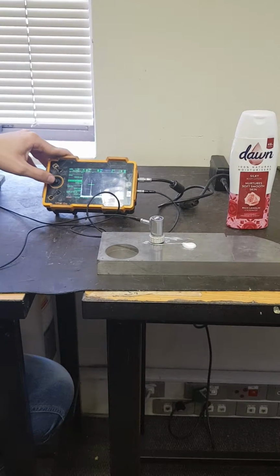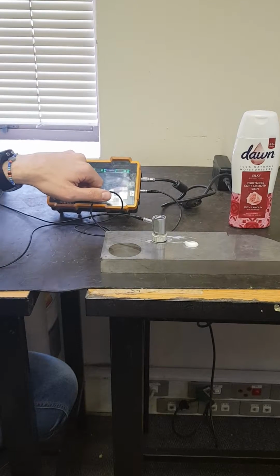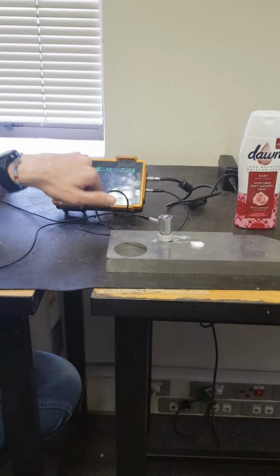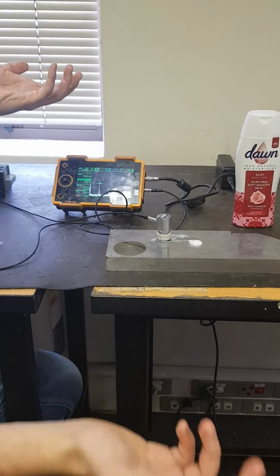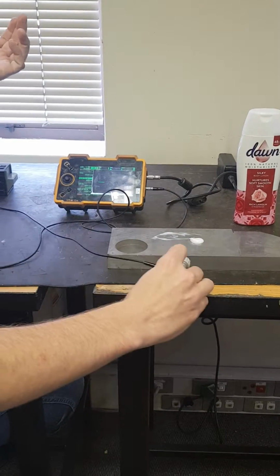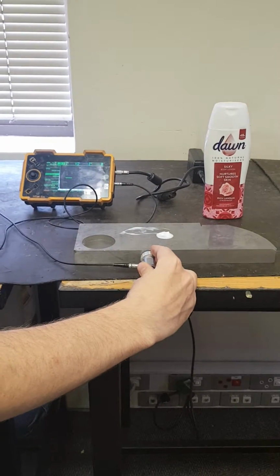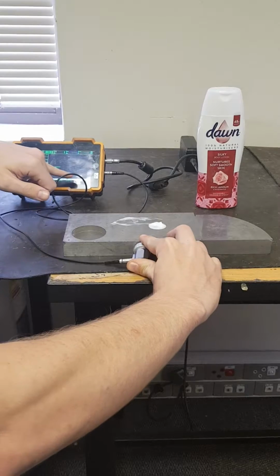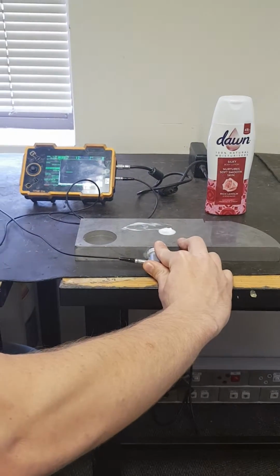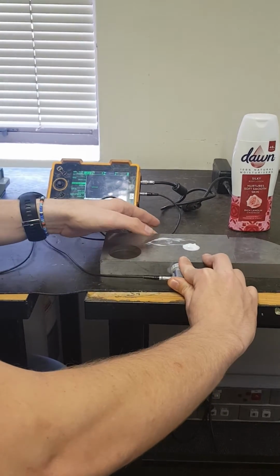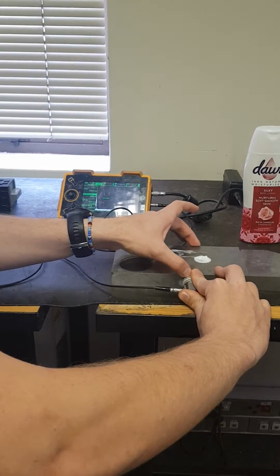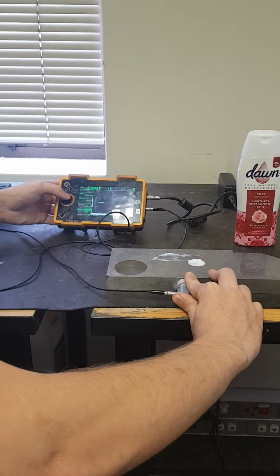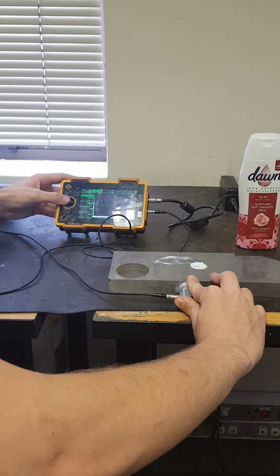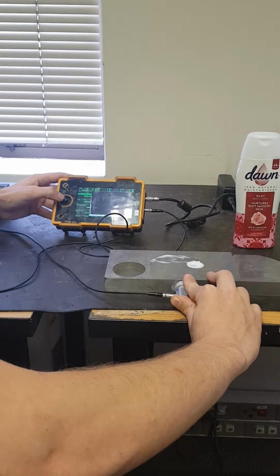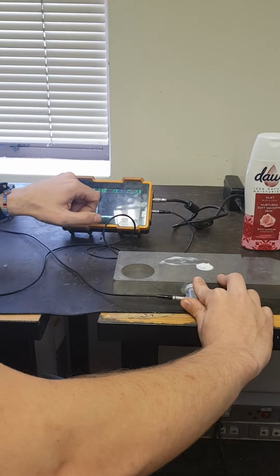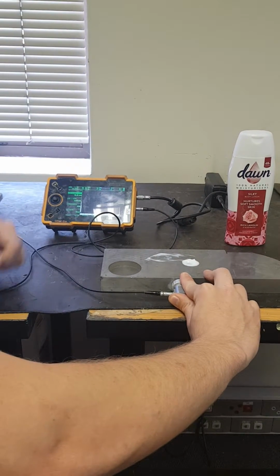until it gives us the exact thickness of the V1 block. Do you see there, it's giving me a reading of 25. What is the thickness of the V1 block? 25. So all's good. What we do next, we take a little bit more lotion or couplant. We couple it here to the end, and you should see at the very end of my range, the echo pops up. Because this block is 100 long and the range is 100, it will pop up exactly at the end. So you take your gate and move it to about 95, and you see it's out on 100 mils by about 0.2 millimeters.